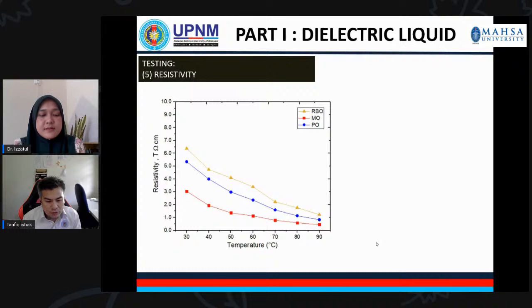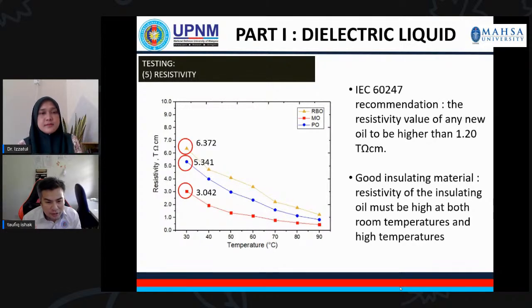All right. Now we look at the resistivity. Everyone knows resistivity is another important electrical property, especially for insulation material, which normally has its unit given in tera ohm centimeter. Any insulation material that has very high resistivity is a very good insulation material. Insulating oil that has very high resistivity normally indicates a low number of free ions and a low concentration of conductive particles, meaning there are not many free ions inside the oil, and also a low concentration of conductive particles inside the oil.